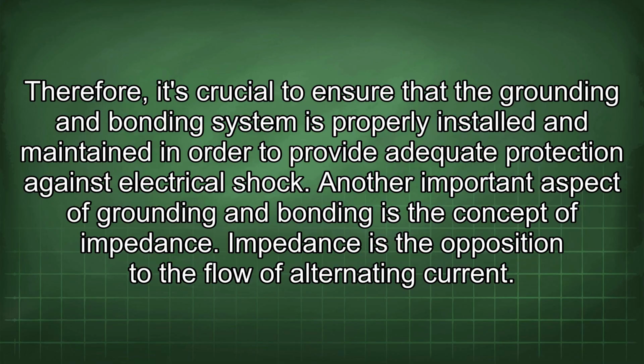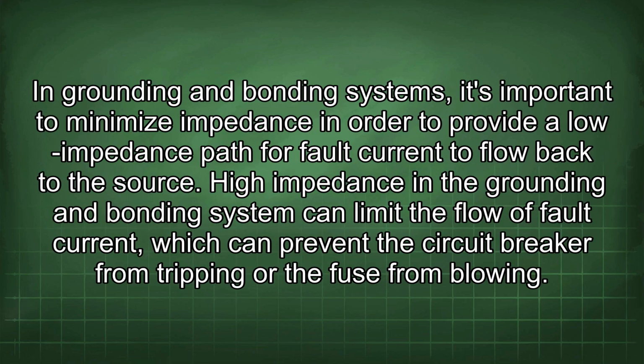Another important aspect of grounding and bonding is the concept of impedance. Impedance is the opposition to the flow of alternating current. In grounding and bonding systems, it's important to minimize impedance in order to provide a low impedance path for fault current to flow back to the source. High impedance in the grounding and bonding system can limit the flow of fault current, which can prevent the circuit breaker from tripping or the fuse from blowing.